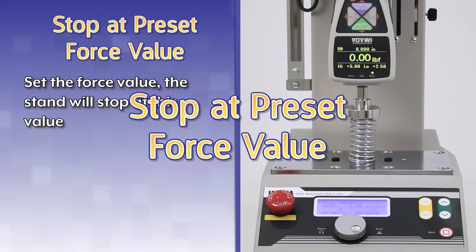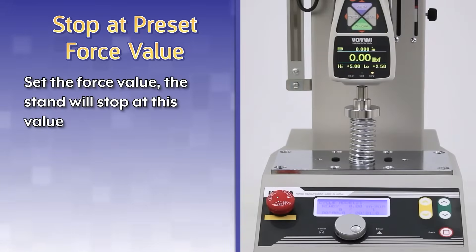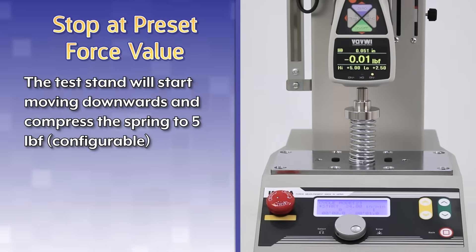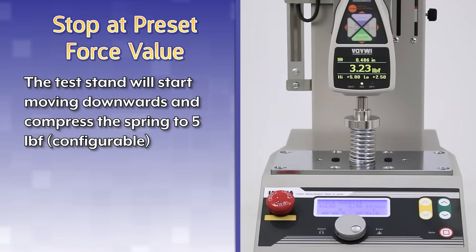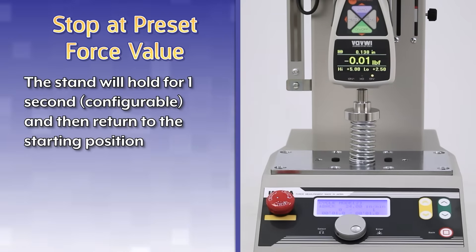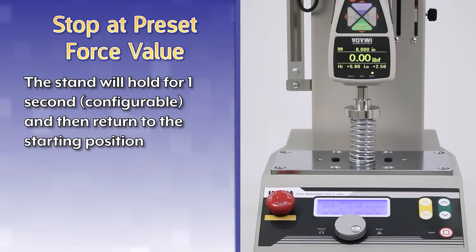Stop at preset force value. Set the force value; the stand will stop at this value. The test stand will start moving downwards and compress the spring to 5 pounds force, configurable. The stand will hold for one second, configurable, and then return to the starting position.